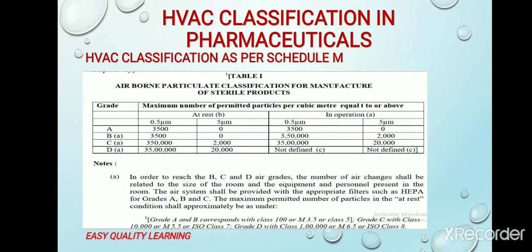This is a snapshot taken from Schedule M. You can see different classes are specified — A, B, C, and D — in which 0.5 micron and 5 micron particles are specified, with the number of particles at rest and in operation given. In Class A and Class B, the particle numbers are the same at static conditions, but in working conditions, Class B allows more particles. These limits are specified for one cubic meter of air.